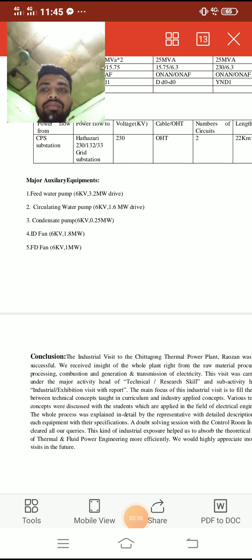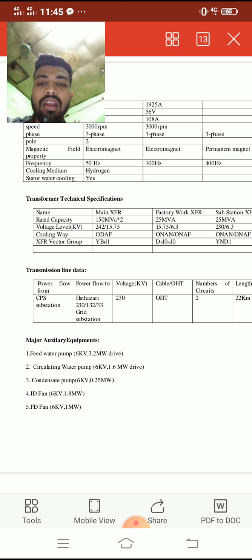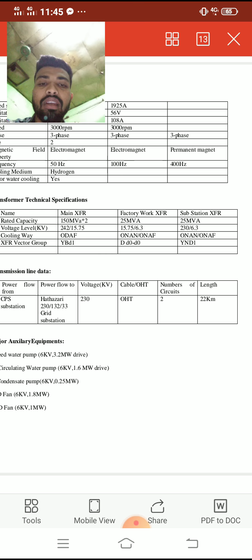Now I will discuss its transformer technical specification. Its cooling oil is ODAF, and power flows from the CPS substation to the Hathazari grid substation. Its voltage is 230 kV, its cable type OHT, number of circuits 2, and its length 22 km.